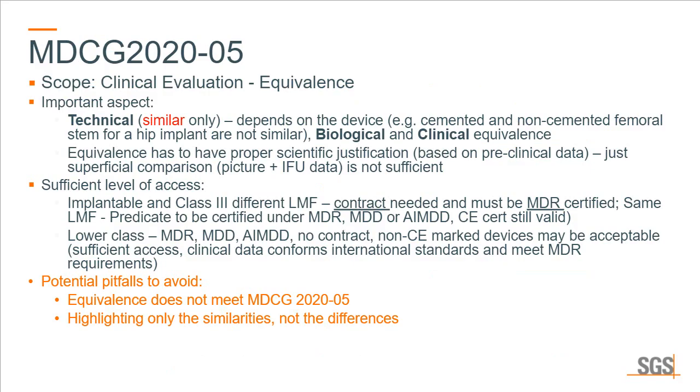All right, so one of the bigger new guidelines, MDCG 2020-05, talks about equivalence of devices. This was already a concept under the MEDDEV guidelines, but now some of the concepts have been refined, and this really is new content to the MDR that was not present under the MDD. The important aspect is that there are three dimensions of equivalence: technical, biological and clinical equivalence.